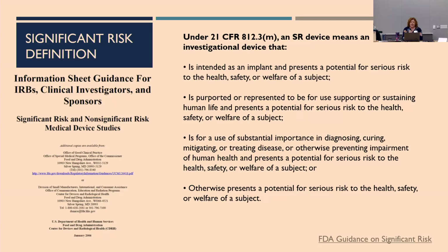So if we take a look at this, one of the key pieces of information they go through is interpreting the regulations. So the significant risk definition comes from, again, the IDE regulations and CFR 812, and they're listed here. So a significant risk device study means that A, it's intended as an implant, presents a potential for serious risk. B, is purported to be sustaining or supporting human life, or there's a serious potential for risk.